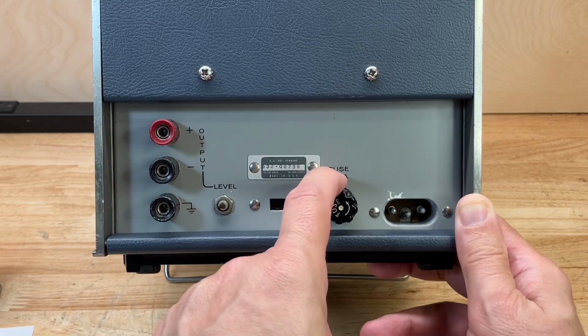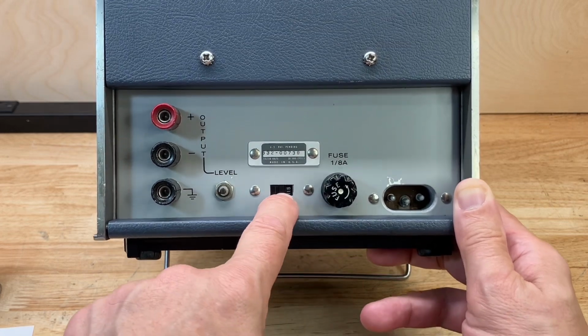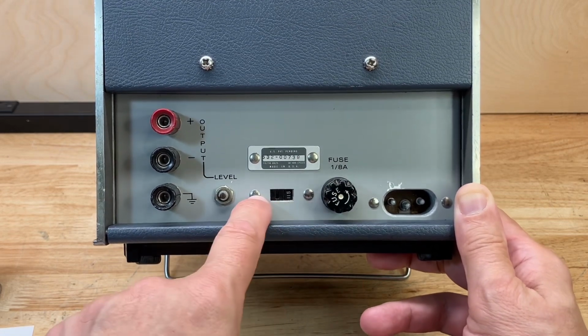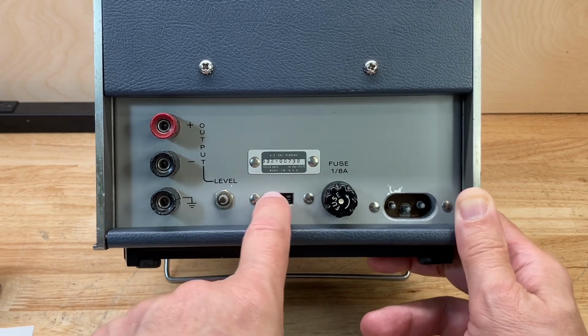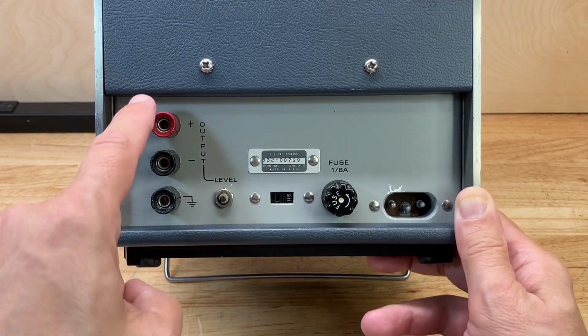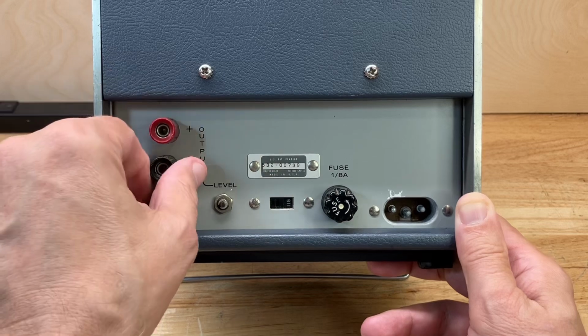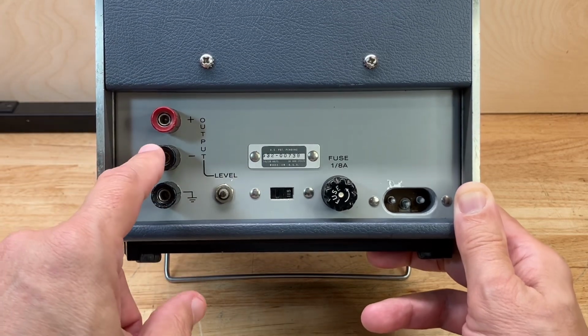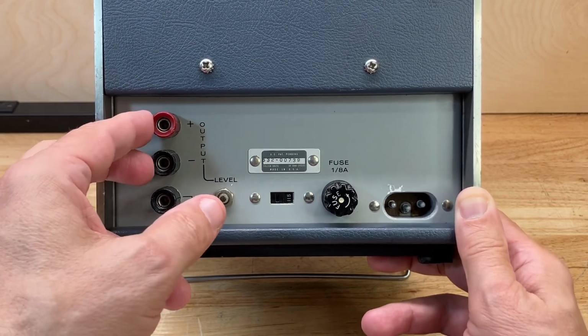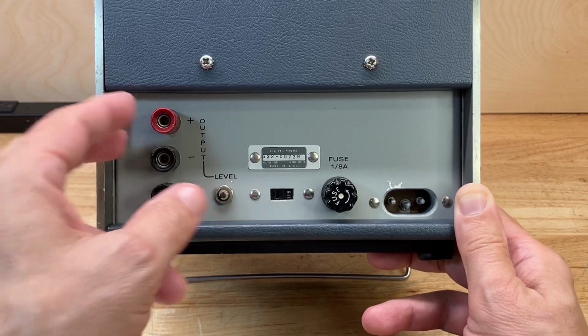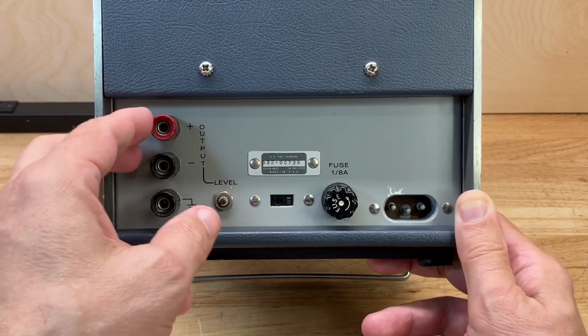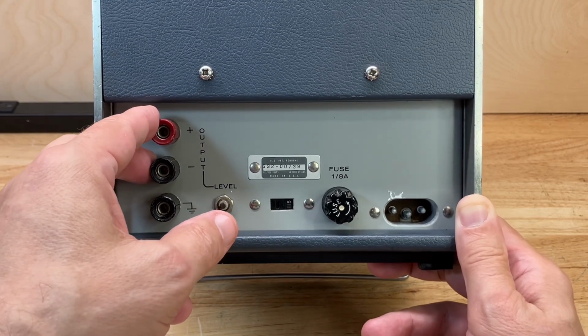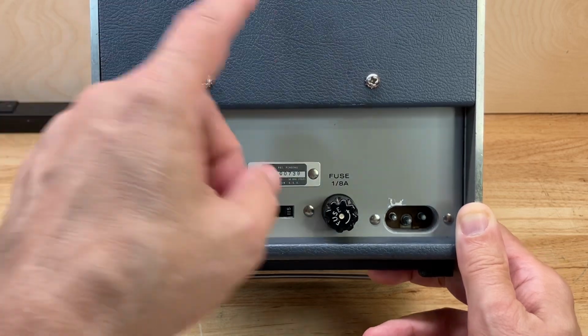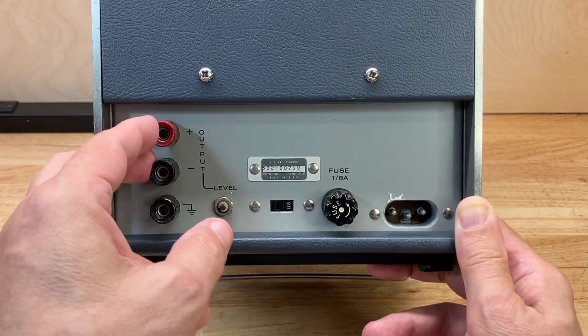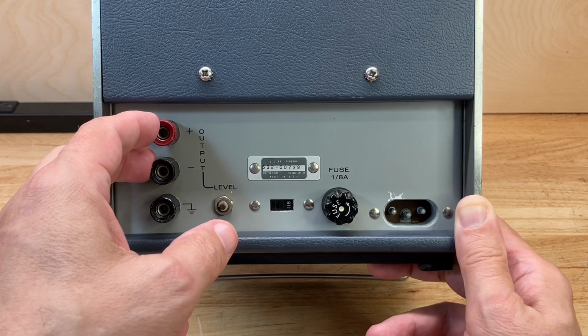It has an input line fuse, 1/8 amp. I've already checked that fuse. It is the correct fuse. A line voltage selector switch, 115 or 230. It is properly set to 115 volts. We have an output on the rear panel. It's a DC voltage output, useful for driving a strip chart recorder or something like that. It's a -1 to +1 volt DC output that corresponds to the measurement on your front panel meter.